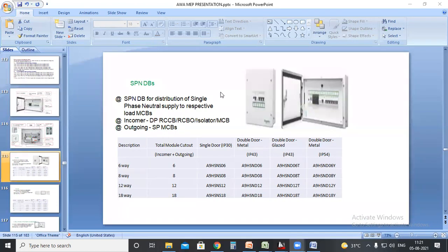36, yeah, correct. So if you have more than 36 circuits, what would you need to do? You need to select another distribution board, because that is the maximum space you can have in a distribution board. For a normal manufactured distribution board, you can have only 36 breakers, 36 circuits. So if, for example, you have 50 circuits for a building, you can't have all the circuits in a single distribution board. So you need to plan accordingly.